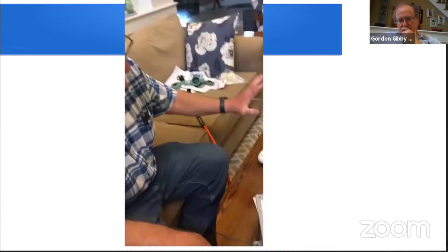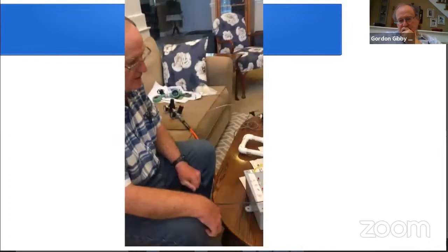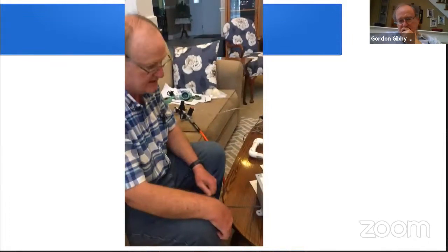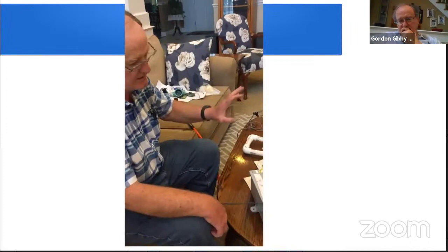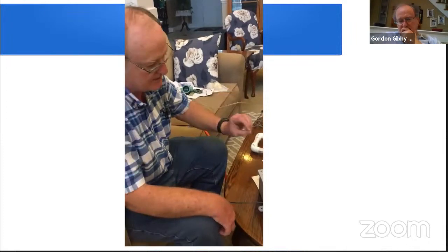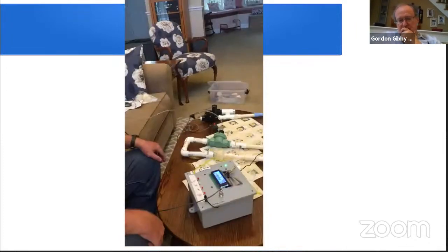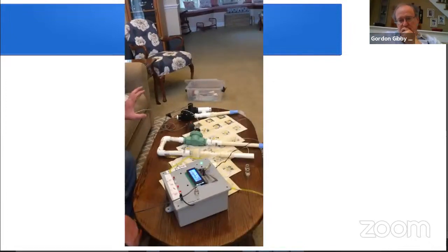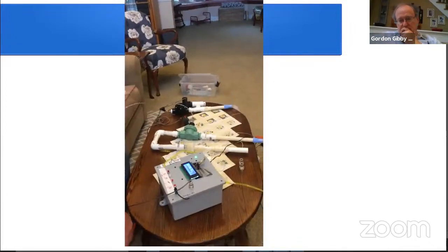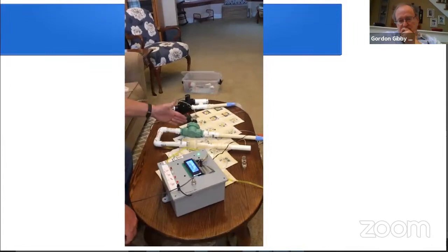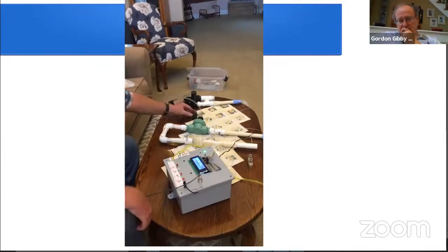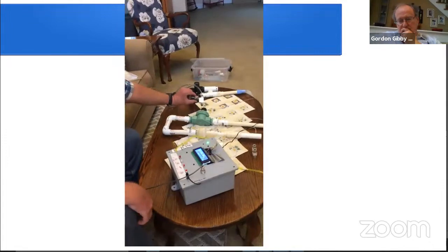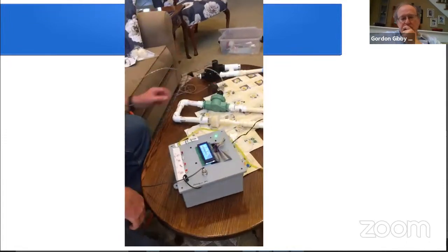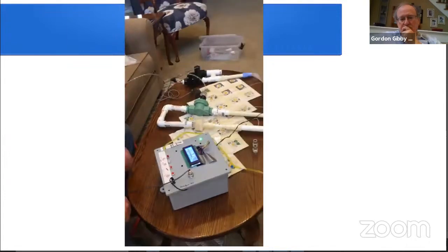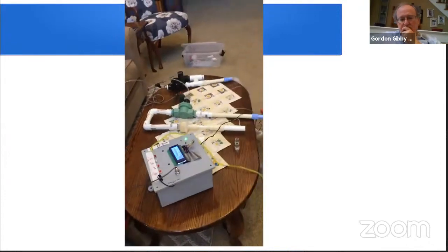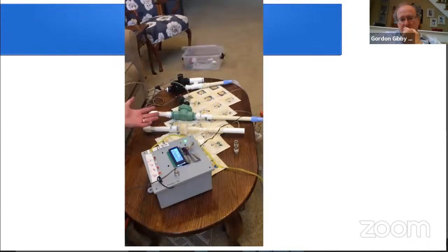This is a different kind of controller. This is a PID controller. Before we were using an adaptive controller. The PID controller tries to deal with the ringing of the system because the air bangs up against the closed valve. The PID controller, a proportional integral derivative controller, actually manipulates this valve on and off very fast. You can see it. This is an LED attached to this solenoid, and it will very quickly hit the correct pressure for the patient. It takes it only a breath, and it's there.